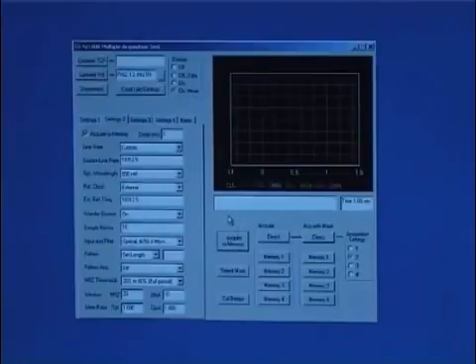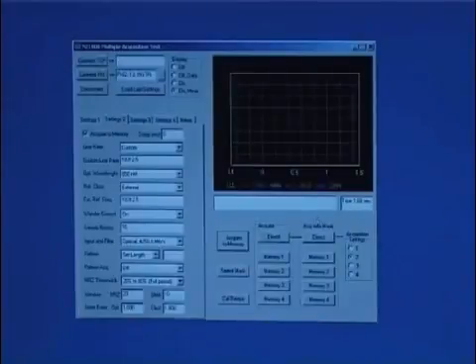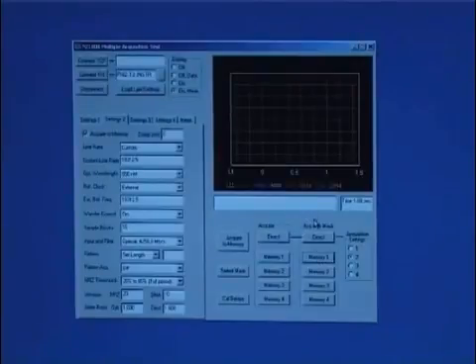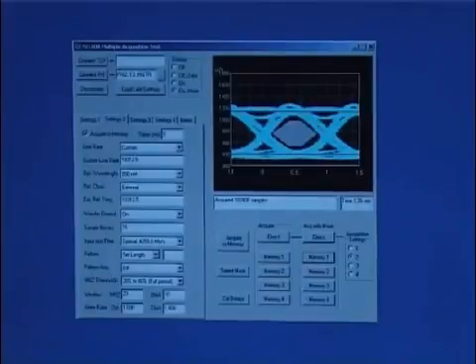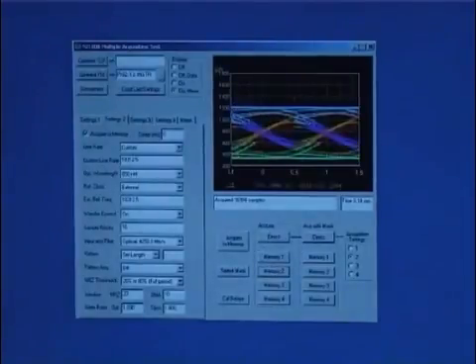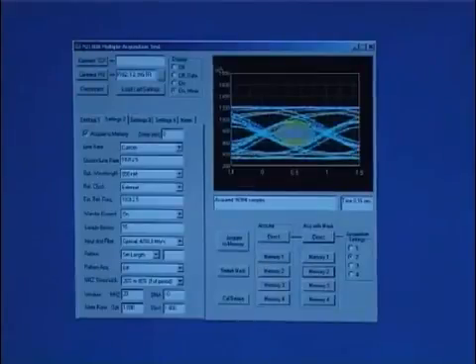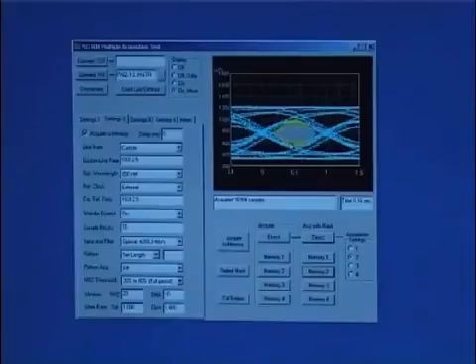Now let's do acquire to memory. At this stage, it's acquired from settings one and the test from settings two, and it took 1.08 seconds. Now I can load that data — either with acquire with mask or a normal acquire. Let's do it with the mask. I select memory one, which was the 100 waveforms. It takes two seconds and it's the 10-gig eye that we see. Let's now select memory two with a normal acquire — we can clearly see that's the 4-gig eye. And selecting memory two with the mask, again, we can clearly see it is the 4-gig path.